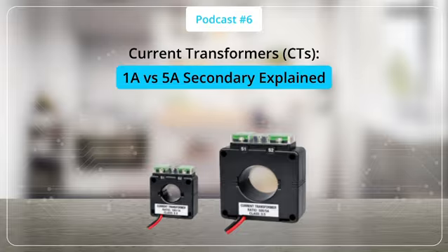Now, let's understand an important concept called CT burden and power loss. Burden refers to the load connected to the CT's secondary side, including wiring, meters, and relays. It is measured in volt-amperes. If the burden is too high, it can affect the accuracy of the CT readings. Another important factor is how current affects losses. When current flows through a conductor, some energy is lost as heat.